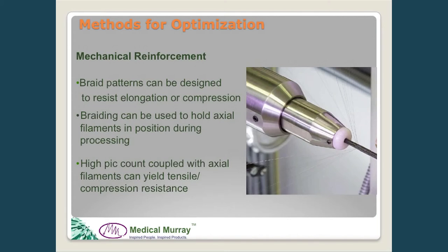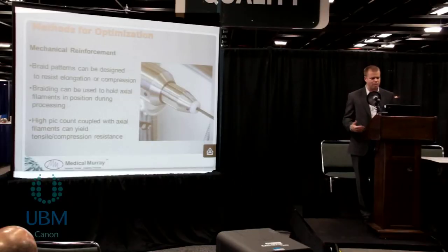Another method for mechanical reinforcement is braid. Braid is commonly used for torqueability within catheters, but in devices with moving components we also need to think about how to design the braid pattern to resist compression and elongation. Braid is also a nice way to hold axial filaments in place — it makes the process repeatable and keeps the filaments straight along the catheter shaft. We can use a combination of braid and axial fibers to achieve both compression and tensile resistance.